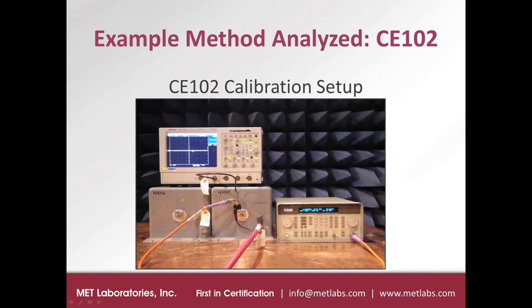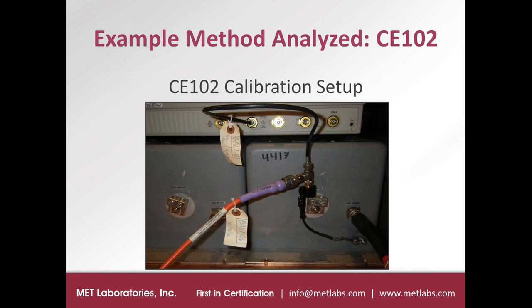Then this red cable is connected to the measurement port, and it's connected to the spectrum analyzer that's out of the view of the photo at the other end. And there's just a close-up of that connection. So this use of the banana to BNC adapter is not described in the standard. That's the solution that we use. You could probably also just strip a coax cable to separate the center conductor from the shield and connect it that way.